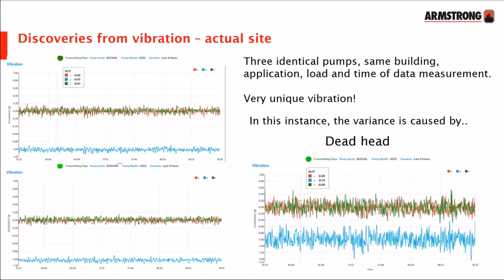You don't need to have an advanced degree in statistics or mathematics to recognise that one of these pumps is experiencing a different level of stress. In this particular instance, the pump at the bottom right of your screen is experiencing a deadhead condition: it was running, but there was no flow. This could have been caused by many reasons, probably a closed isolation valve or something like that.